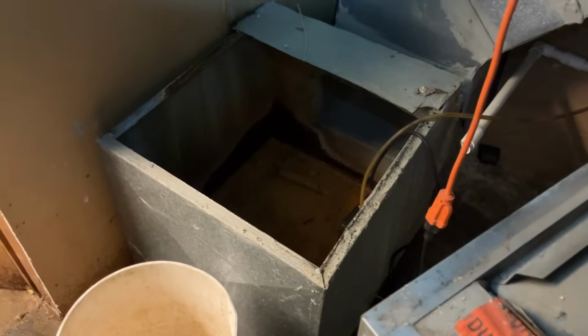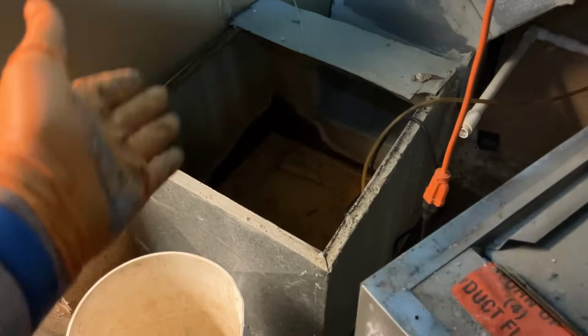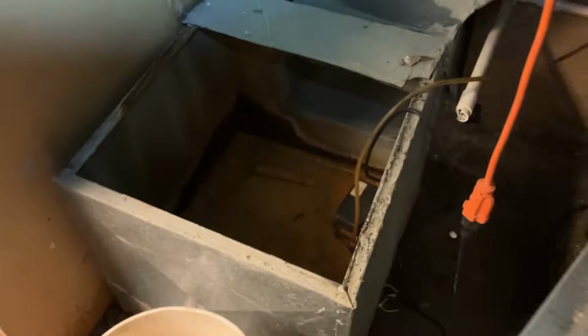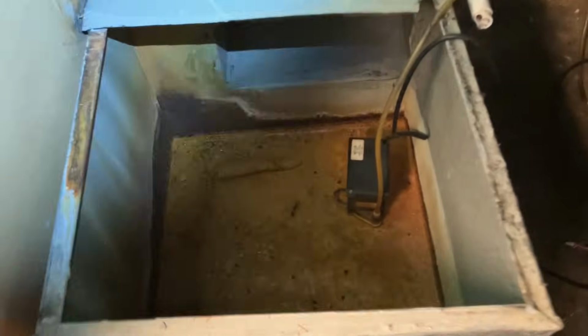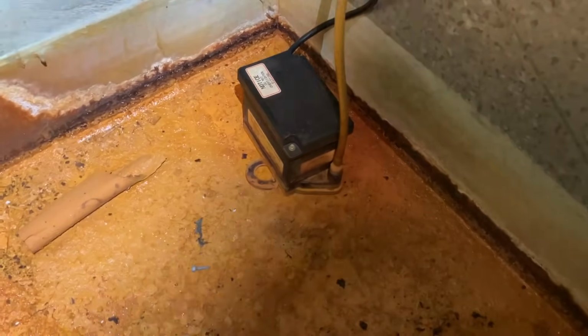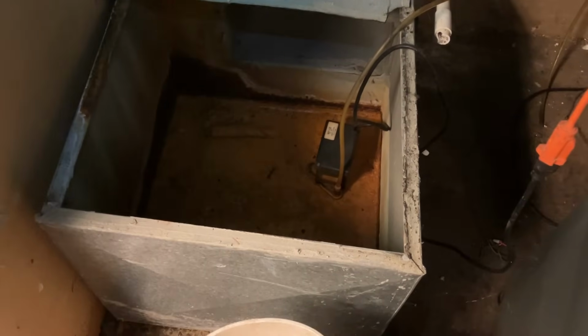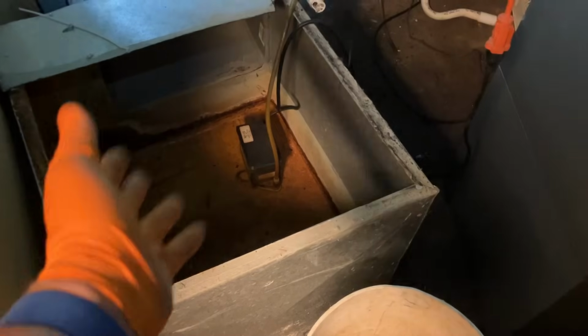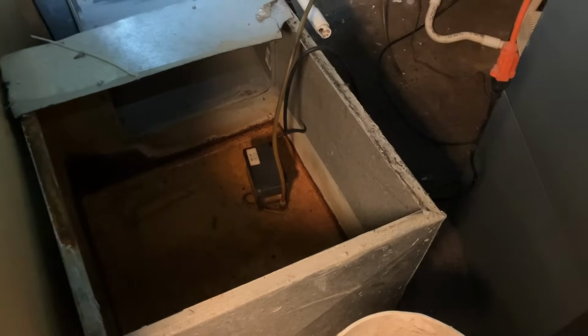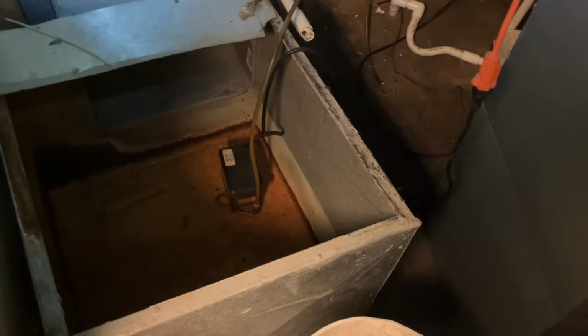But take a look at this, you guys ready? This is the return plenum box, the air handler was sitting on top of it. There's that return plenum coming from overhead, this is an upflow system by the way. And take a look at that, there's a sump pump sitting inside this return plenum box, which I guess turns into like a little miniature pool or a sump pump pit. So instead of fixing the issue of why there's water in the bottom of the ductwork, someone put a condensate pump in it and pumped it into the other pump, and then it went away. Genius, absolutely genius.